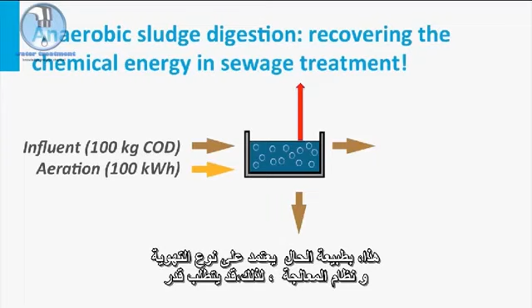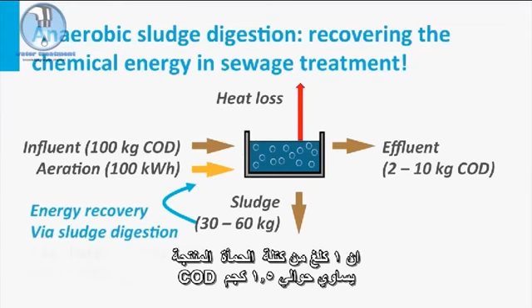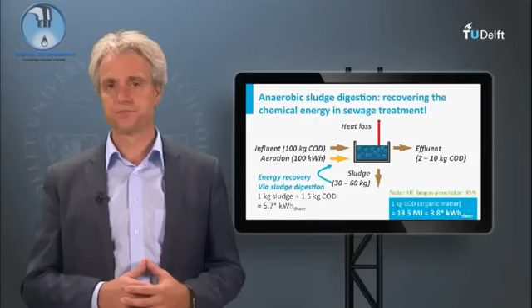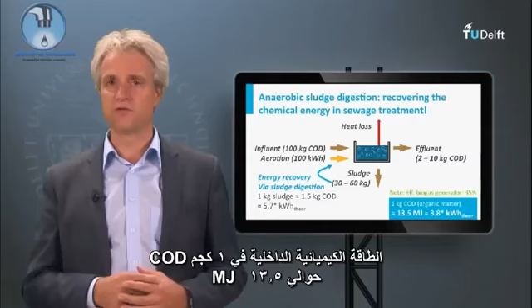Meanwhile, a high amount of sludge mass is produced. From the incoming COD, about 50% will end up in the biomass produced. The rest of the energy that is liberated in the process will leave the system as heat. 1 kilogram of produced sludge mass equals about 1.5 kilogram of COD. The chemical energy enclosed in 1 kilogram of COD is about 13.5 megajoule, which theoretically equals about 3.8 kilowatt hours.